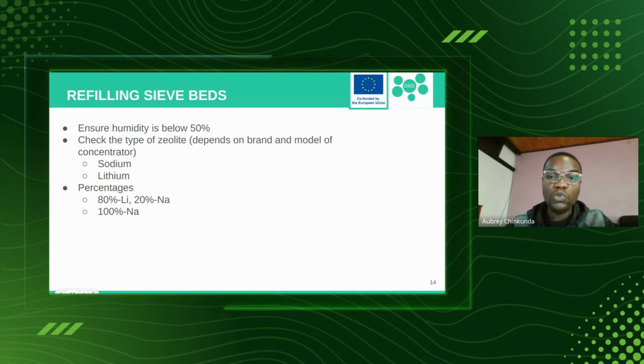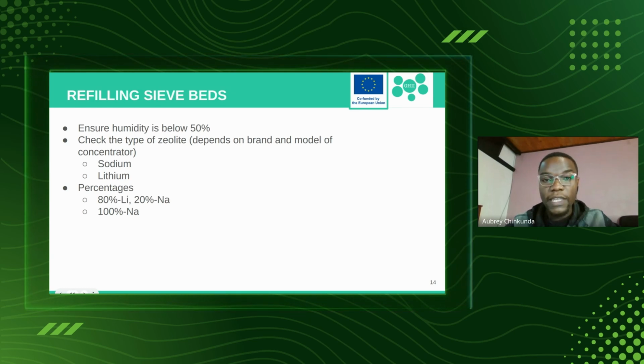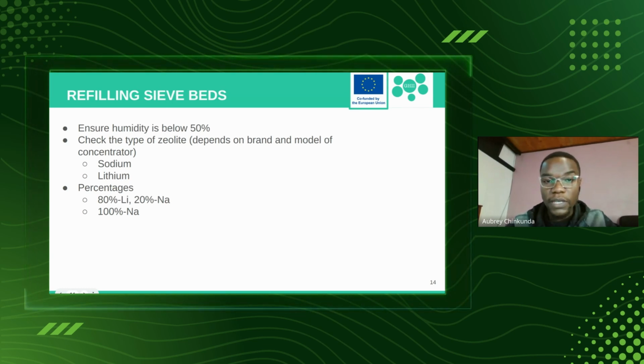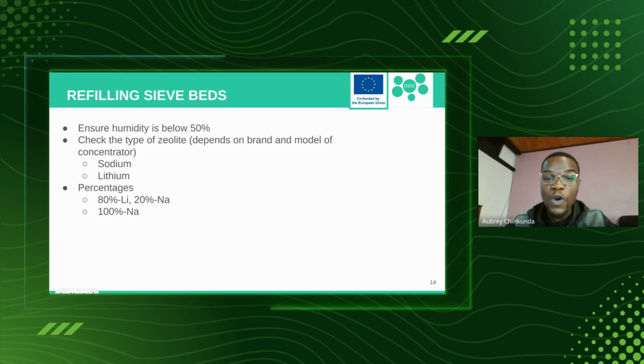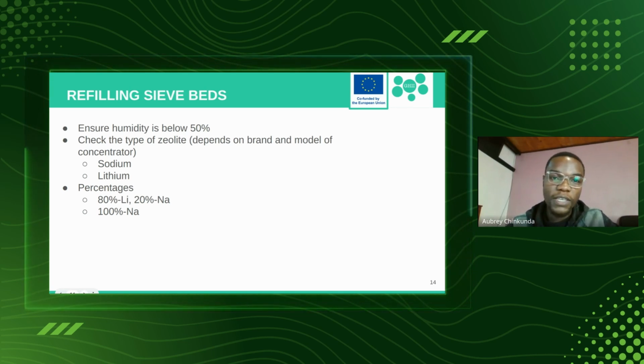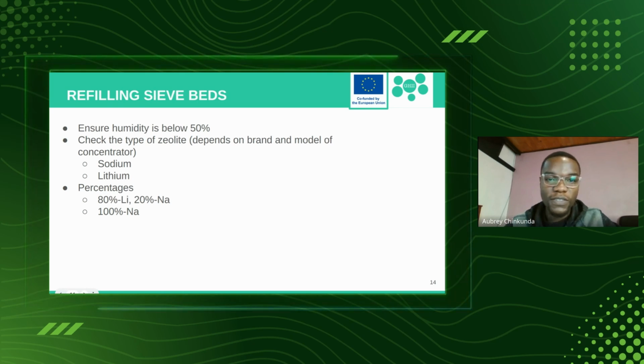You also need to check the type of zeolite the concentrator uses, which differs by brand and model. Some use sodium, some use lithium, so you always need to be sure which zeolite you're using. You don't want to replace lithium zeolite with sodium zeolite, or you might have issues, since lithium is a bit more efficient than sodium. You might refill and then not get the appropriate oxygen purities.